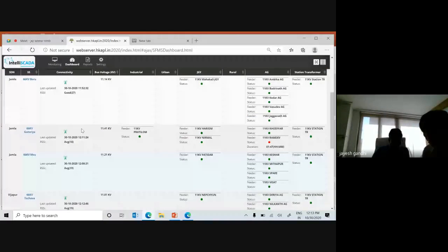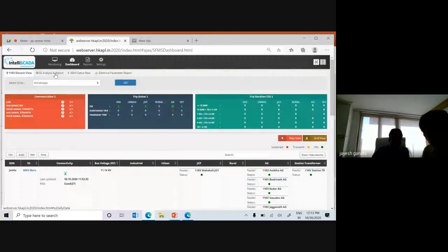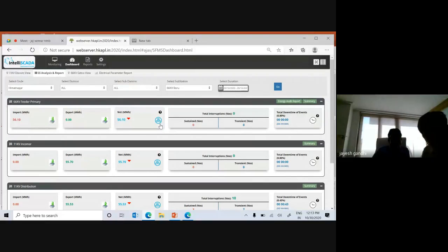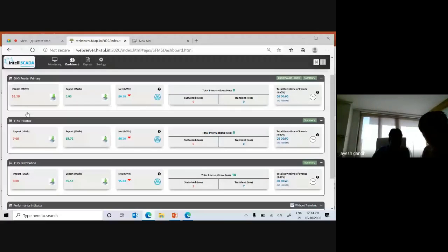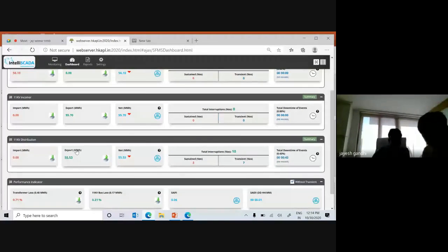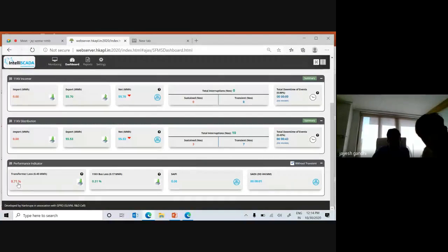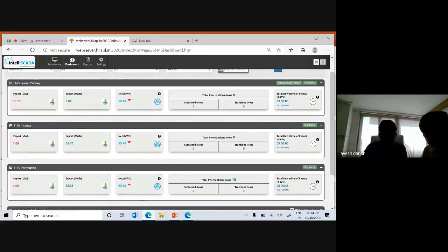And now we will talk about the losses dashboard. Here you can see that 56 megawatt units is received at the substations, and 55.53 megawatt units sent out from the substations. So here you can see the transformer losses is 0.71%, and the bus losses is 0.31%. So transformer loss is nothing but the difference between incoming power and outgoing power.